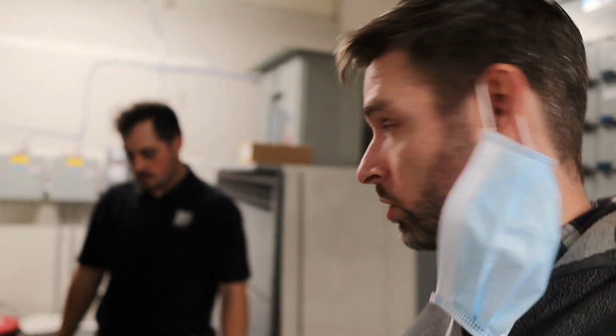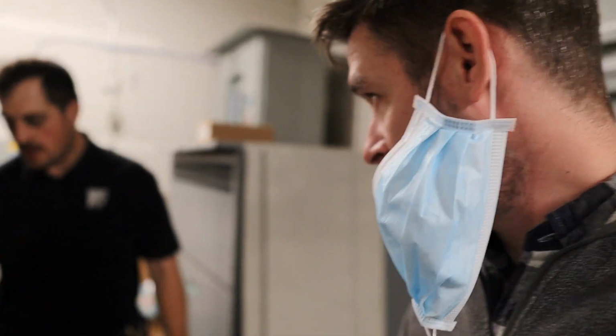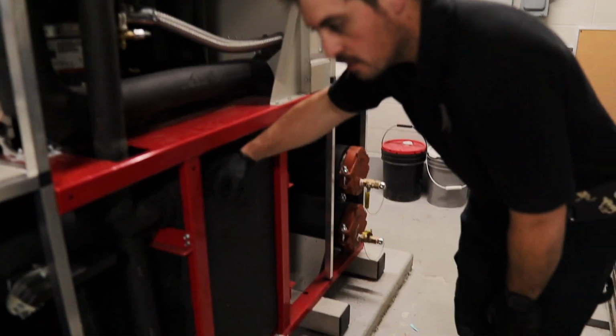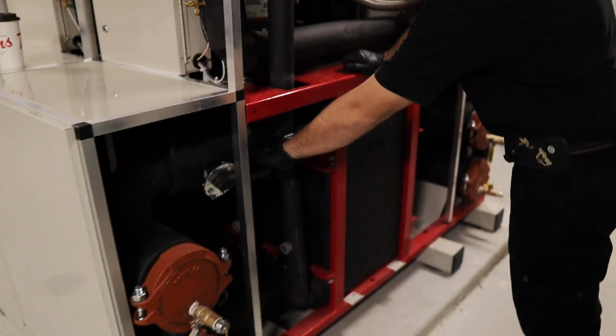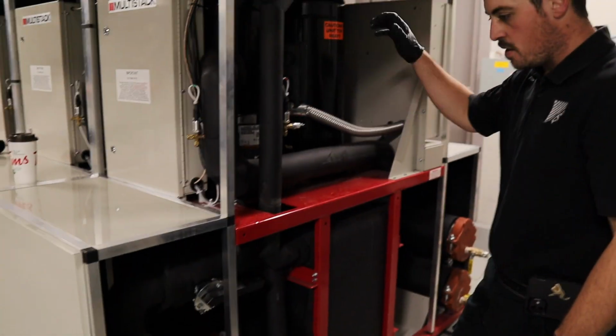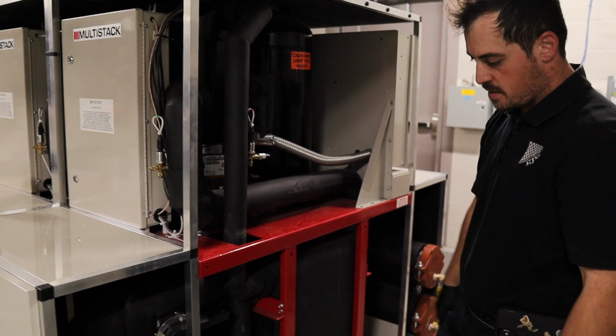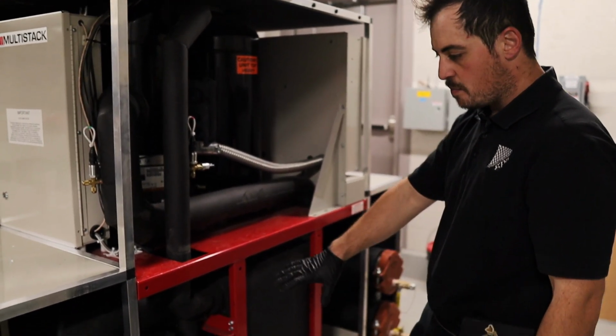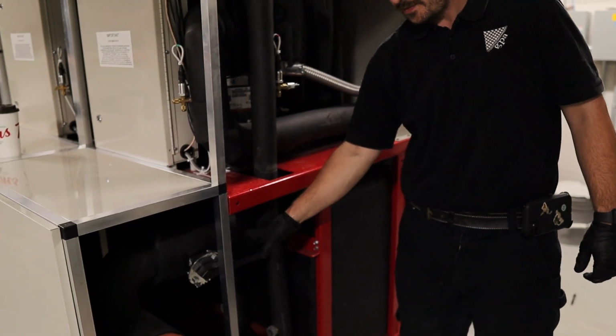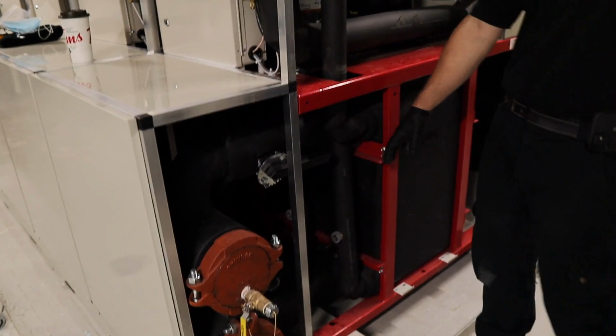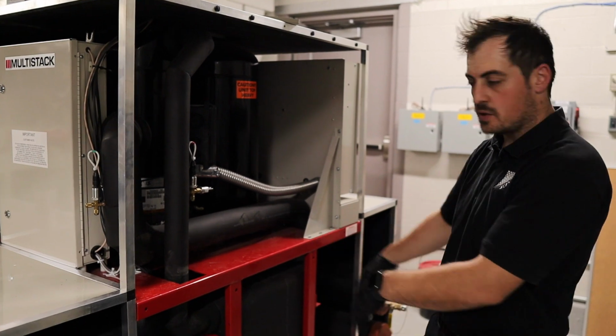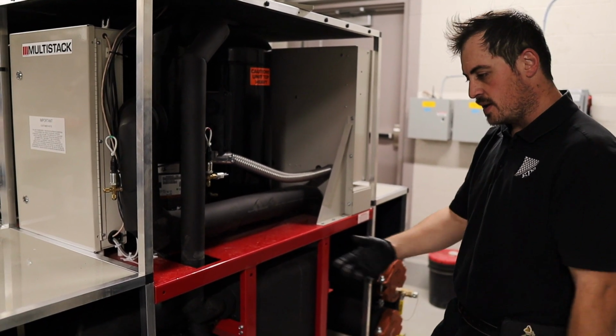So Dennis and I are just here talking about the setup of this particular Multistack heat recovery chiller. It's a little different than the one we looked at over in the other mechanical room. This one has something called total access design. Dennis, can you tell us a little bit about what that is? For this particular model, the total access allows you to isolate an individual circuit from the rest to complete maintenance on it, or some kind of repair, where you don't have to drain the entire chiller. You could just isolate it, release, open the Victaulics, and drain that one circuit, complete your repairs, in the event you have to drain the water.